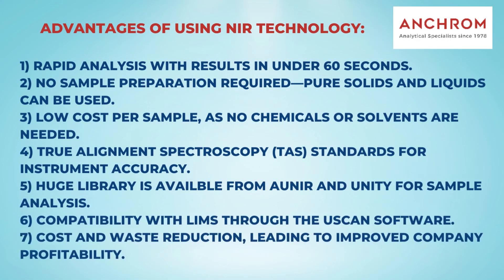Let's recap the advantages of using NIR technology: 1. Rapid analysis with results in under 60 seconds. 2. No sample preparation required — pure solids and liquids can be used. 3. Low cost per sample, as no chemicals or solvents are needed. 4. True Alignment Spectroscopy (TAS) standards for instrument accuracy. 5. A huge library is available from AUNIR and Unity for sample analysis. 6. Compatibility with LIMS through the uScan software. 7. Cost and waste reduction, leading to improved company profitability.